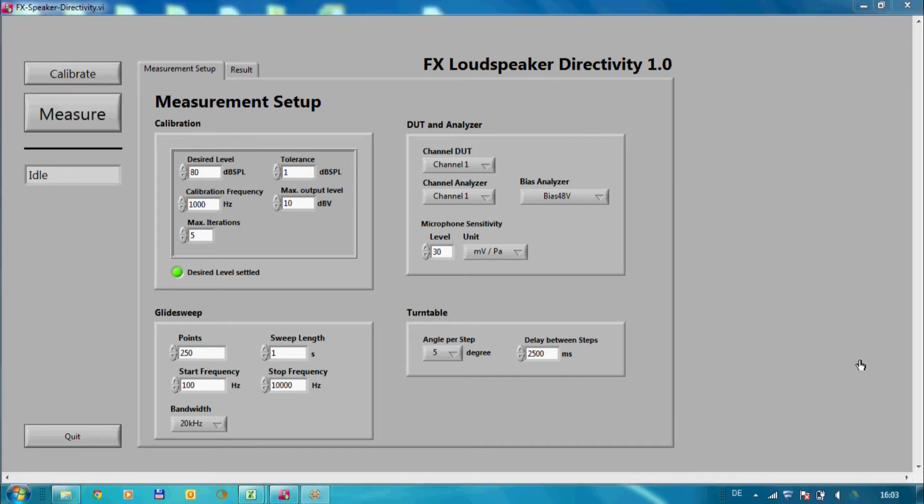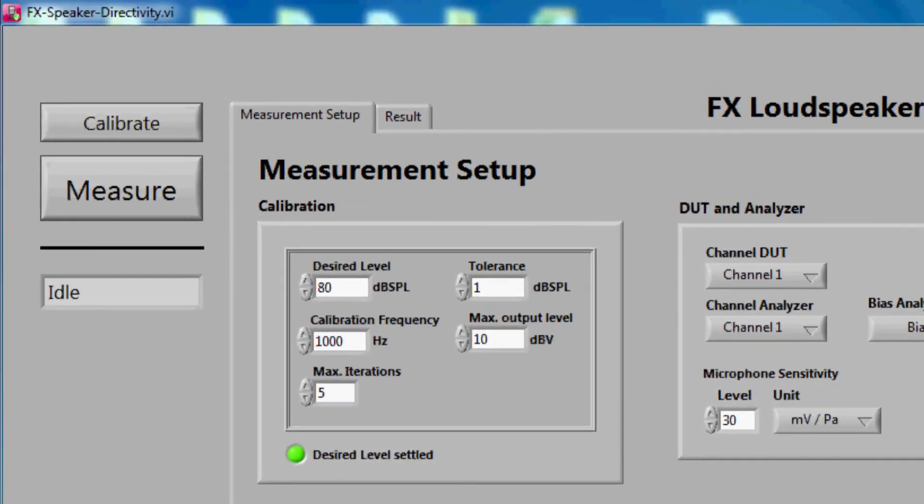The LabVIEW application will now find the appropriate generator output level to match with the defined sound pressure level. If the level could be settled, the measure button gets enabled and the indicator will turn to green.